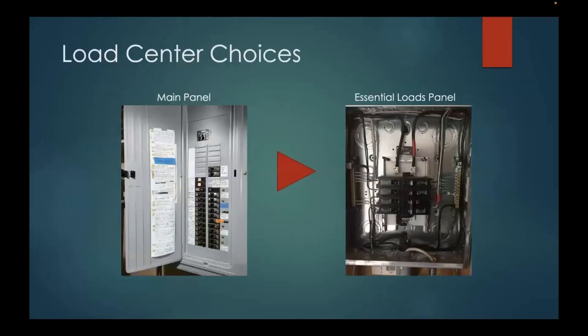Now we have some different load center choices. The main panel is that big breaker box next to your meter, or your meter's attached to it, and it has all the loads in your house. Or you can do an essential load panel, backup panel, protected load panel, where you just put 6 circuits on there. This one has 8, but yeah.